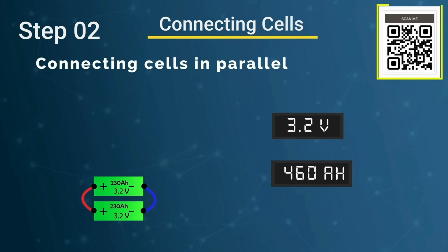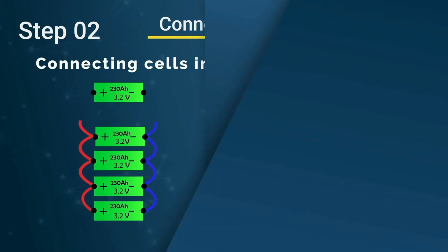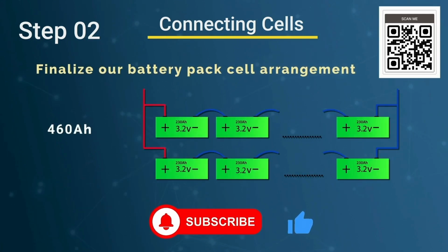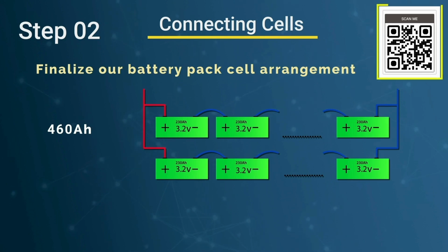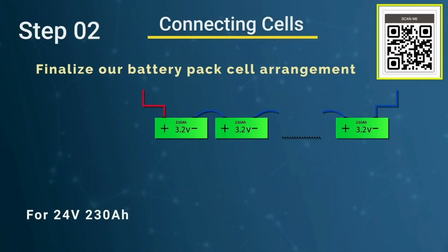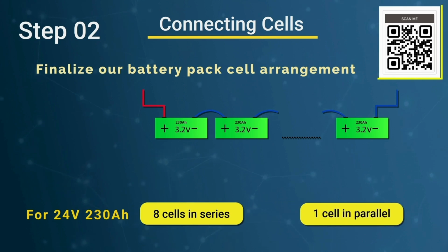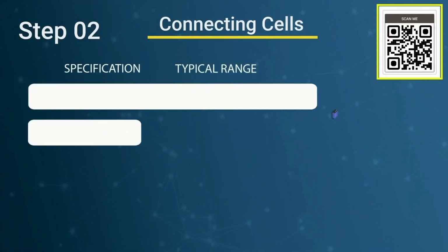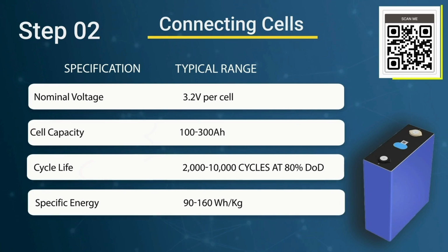Connecting cells in parallel increases the capacity. If you want to build a 460 ampere-hour 24-volt battery pack, then you need to connect 2 sets of 230 ampere-hour cells in parallel. Now we are going to finalize our battery pack cell arrangement. For our 24-volt, 230 ampere-hour pack, we will need 8 cells in series and 1 cell in parallel. This means that 8 cells are connected in series to achieve 24 volts, and only 1 set since we achieve 5 kilowatt-hour capacity. Before buying LiFePO4 cells, we should consider their specifications and price.